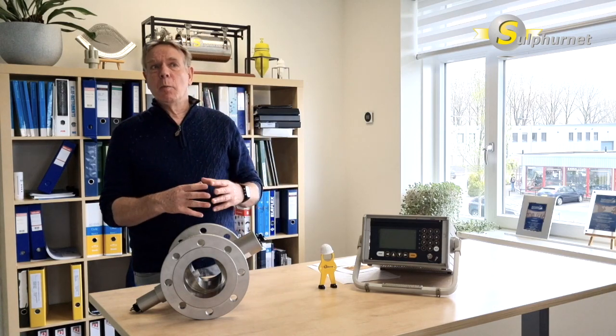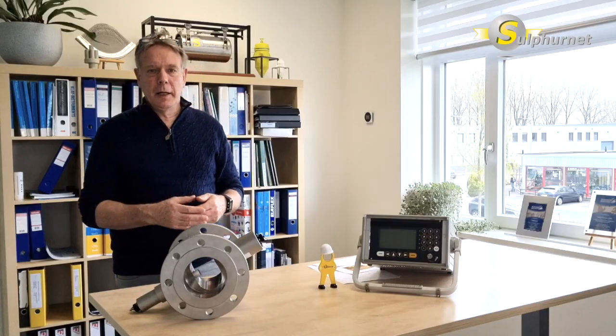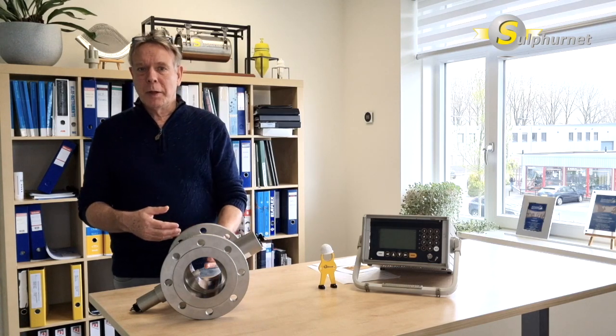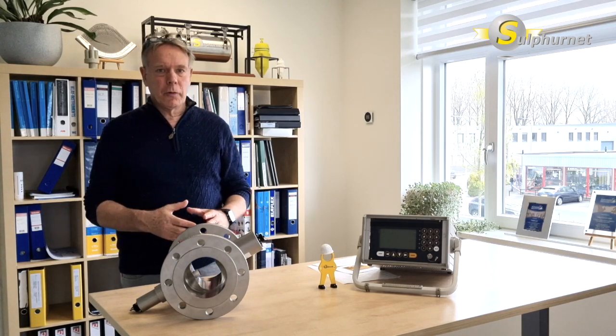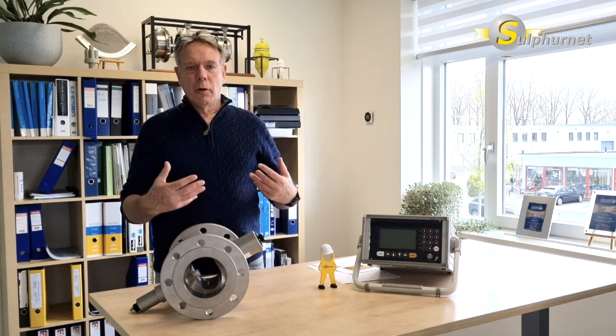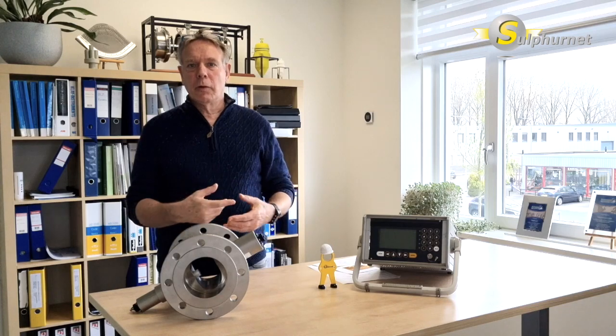All these costs can be between 1 and 2 million euros. And if you install a system like that, you can extend the intervals between the cleaning from 20 months to 28 or even more months. And that means that your catalyst bed is protected and your operation and maintenance costs are reduced drastically.